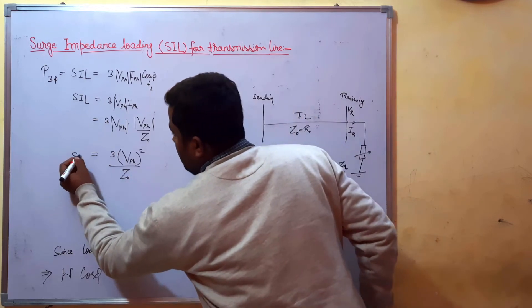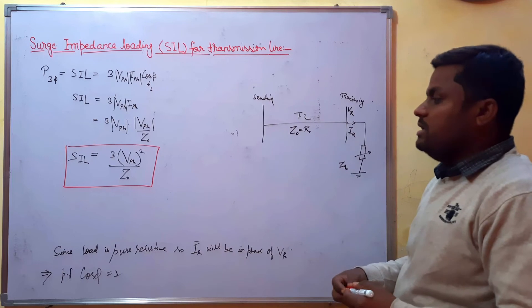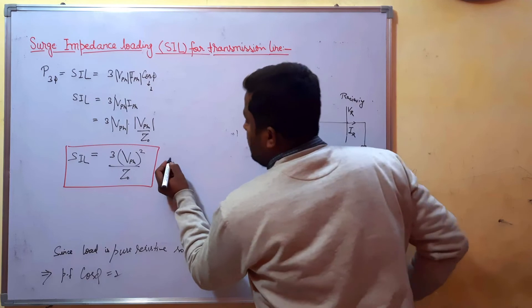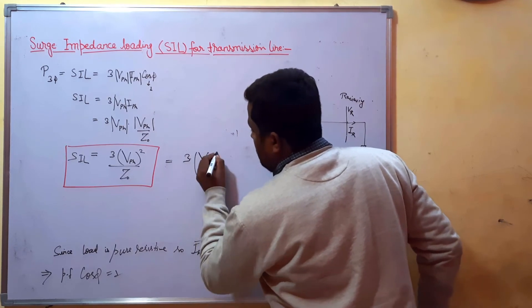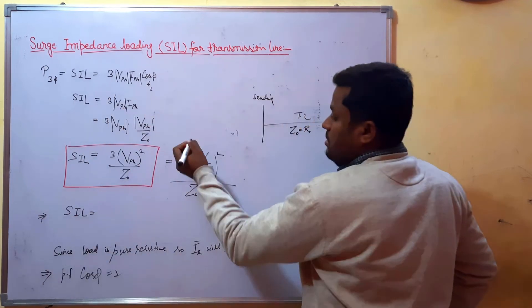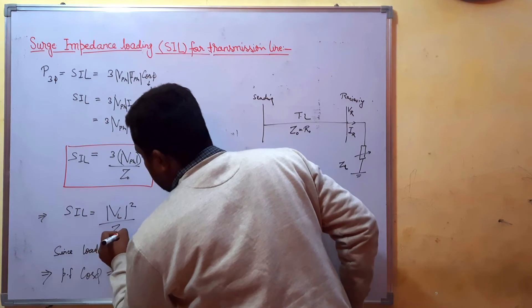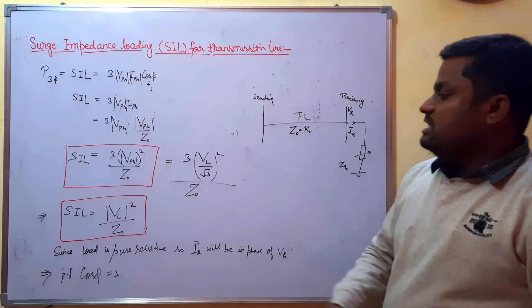Therefore, SIL = 3 × Vphase² / Z0, where Vphase is the receiving end voltage per phase. If we express the receiving end voltage in terms of line voltage, where Vphase = VL / √3, then SIL = VL² / Z0. This is the formula for surge impedance loading of a transmission line.